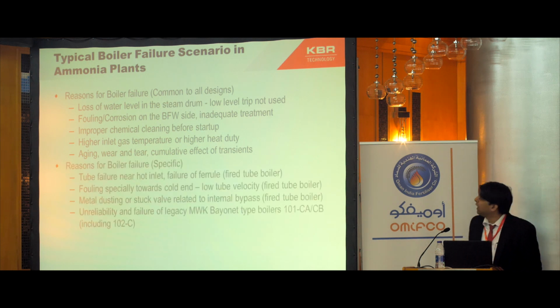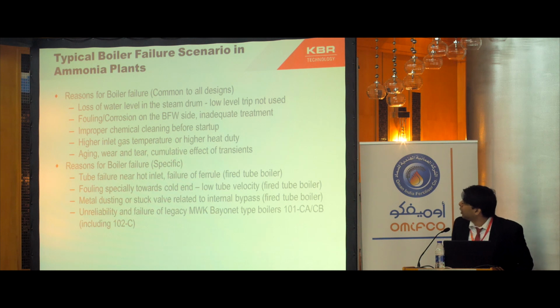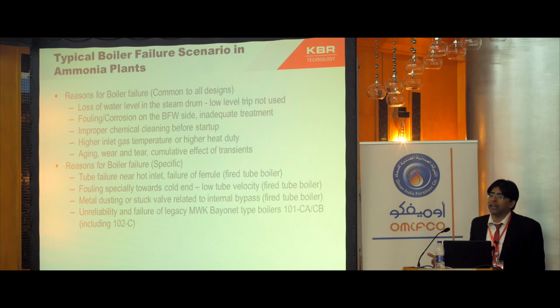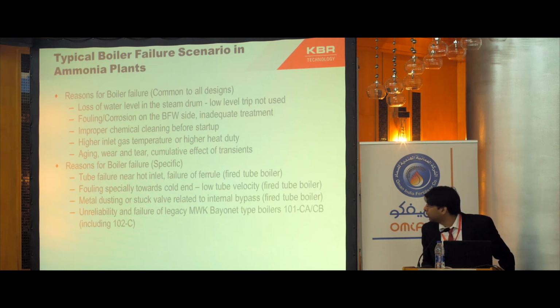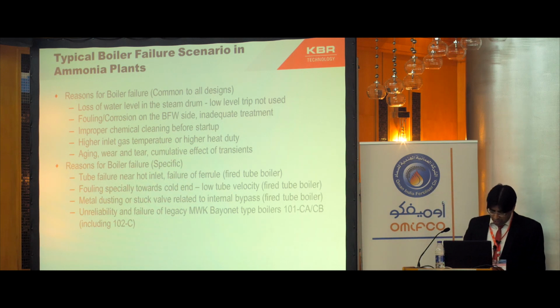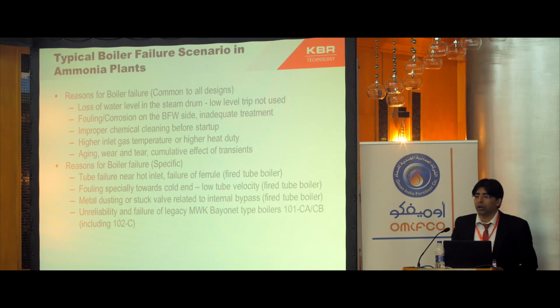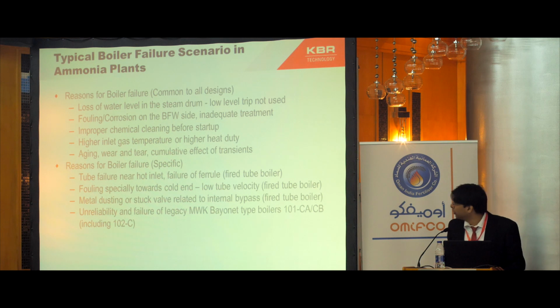Coming to the specific failures for the design of this boiler, for the fire tube boiler, it can be failure of ferrule or the fouling in the cold end. Sometimes metal dusting or a stuck valve in the internal bypass can also lead to the failure of this boiler. Also, the unreliability and failure of the legacy MWK Bayonet design, which I'm going to discuss in the next slide.